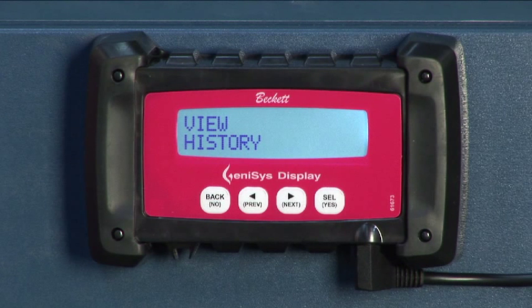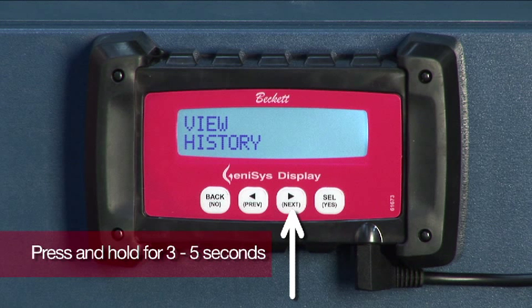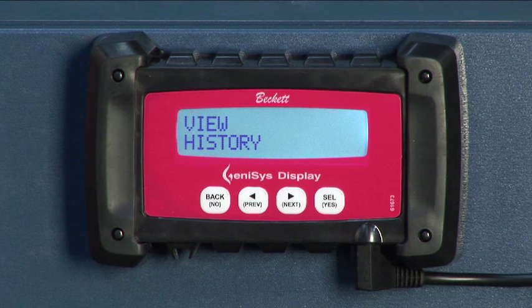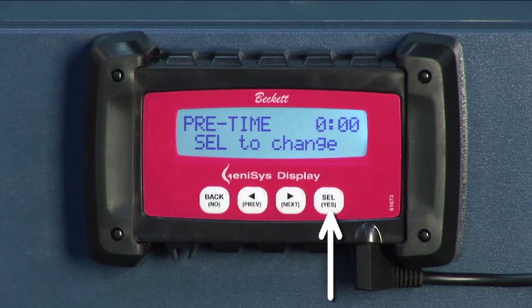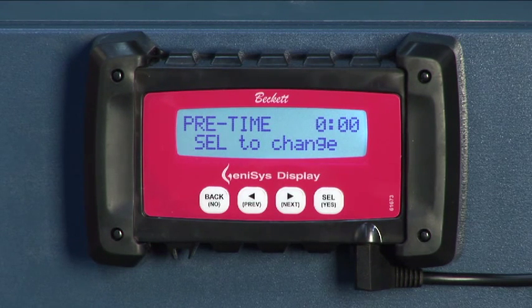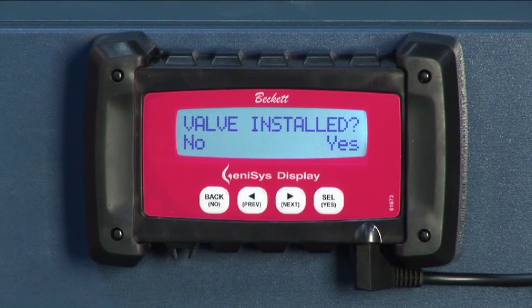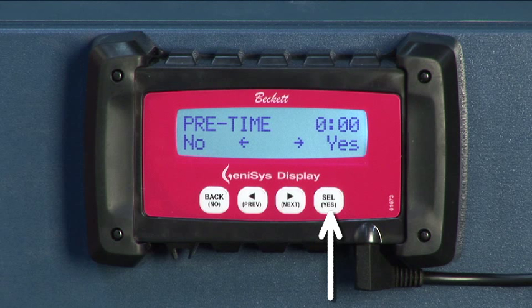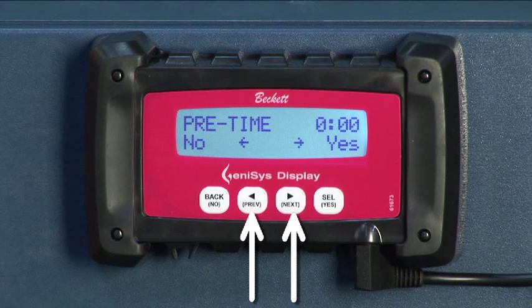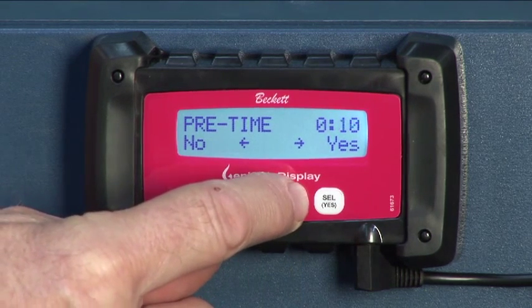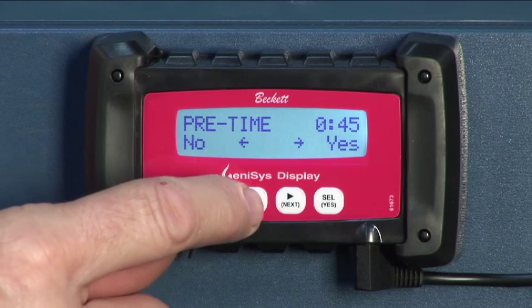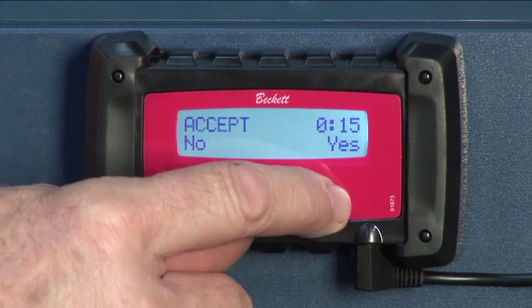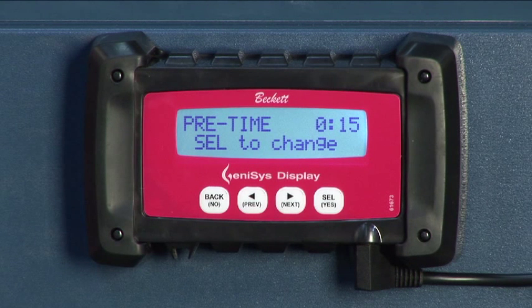From either the view history or the burner status screens, press and hold the next key for 3 to 5 seconds. If the control is on, the pre-time screen will be displayed showing the current pre-purge valve-on-delay time setting. Now we'll press SEL yes to change this setting. If the setting is 0, the display will ask if a valve has been installed, which it needs to operate in pre-time. Next, press SEL yes once the valve is installed. Then use PREV and next to select 0, 5, 10, 15, 30, or 45 seconds as the pre-time setting. Confirm the selection with SEL yes, or cancel the change by pressing back no, which will display 'change cancelled' and return to the initial pre-time select to change screen.